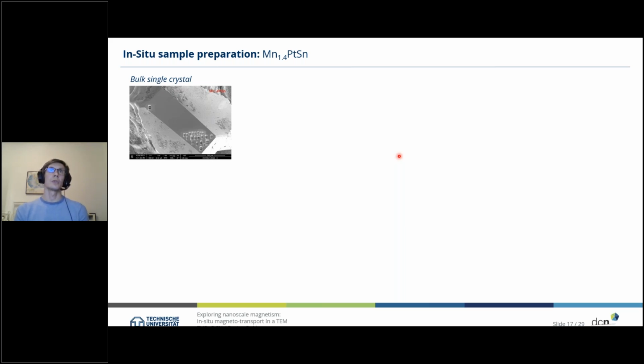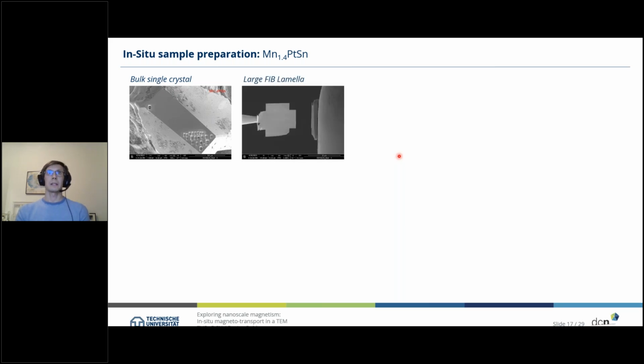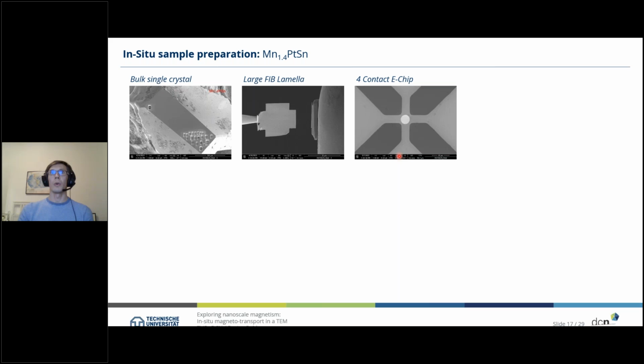Instead, we need to cut out small pieces, lamellas, out of that bulk single crystal, where we then have a large FIB lamella, which needs to be very homogeneous and especially with the same thickness, if possible, and a very low thickness of 100 to 150 nanometers over the whole lamella. Then we place this onto the commercially available 4-contact E-chip, where we cut in a small hole in the center.